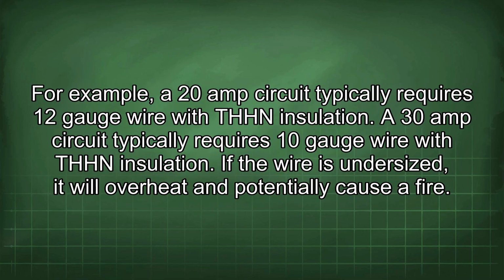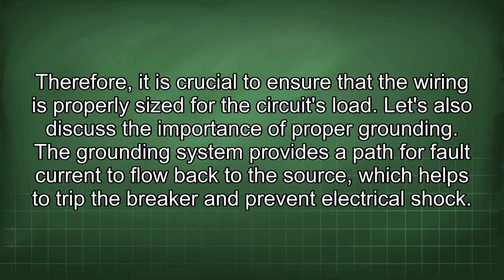For example, a 20-amp circuit typically requires 12-gauge wire with THHN insulation. A 30-amp circuit typically requires 10-gauge wire with THHN insulation. If the wire is undersized, it will overheat and potentially cause a fire. Therefore, it is crucial to ensure that the wiring is properly sized for the circuit's load.